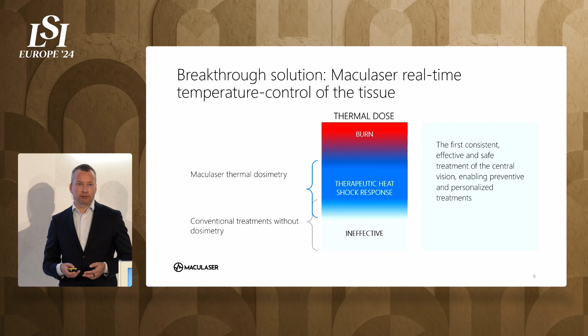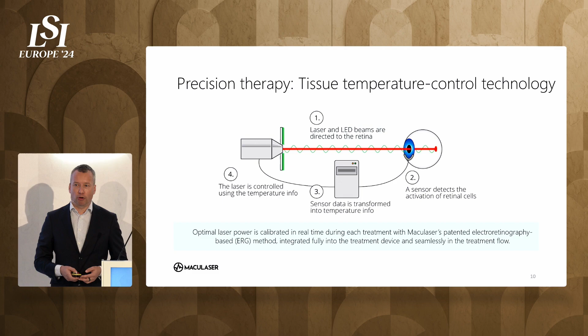How do we do it? We have built a sensor system to be combined with non-damaging laser systems. So we add flashes of light. These flashes generate an electrical response in the retina. We measure that response with our system, and the sensor data is then transformed into temperature information. When we know the temperature, we can adjust the laser power accordingly and individually.